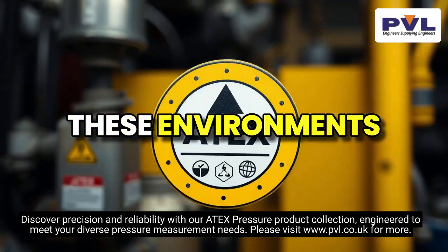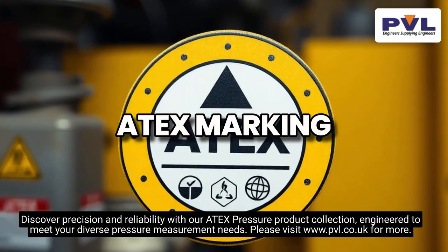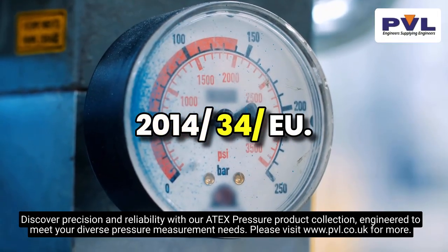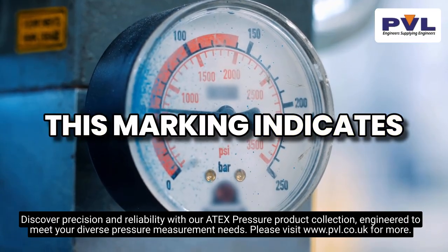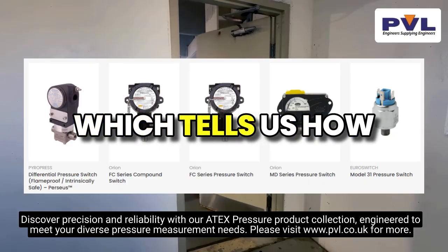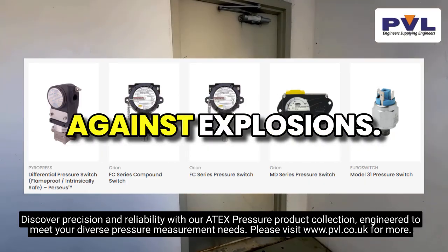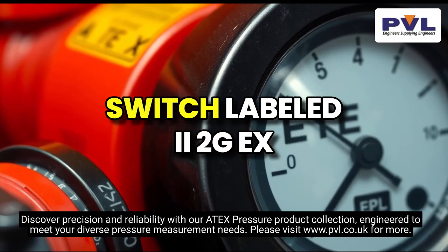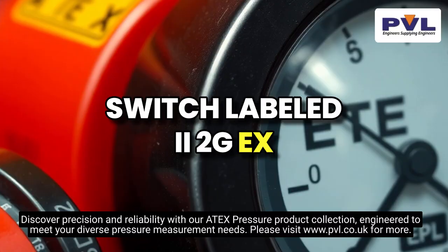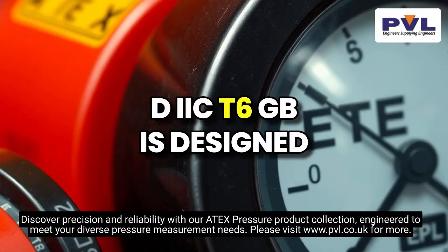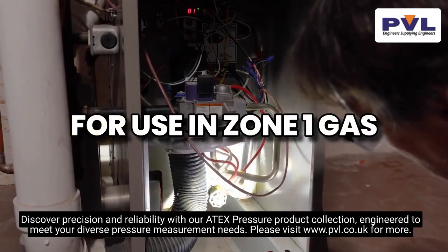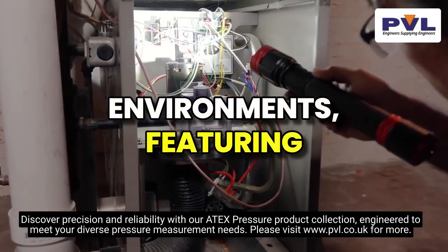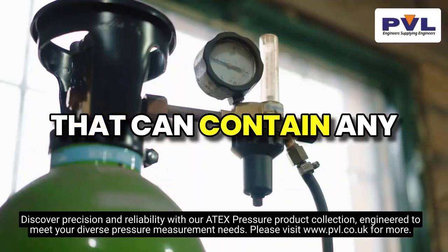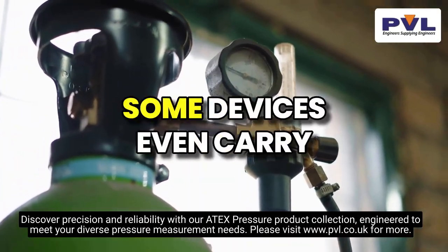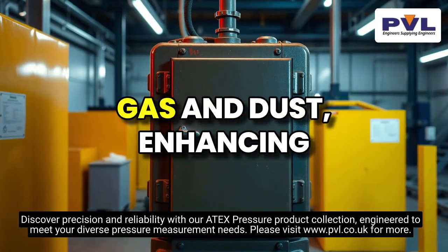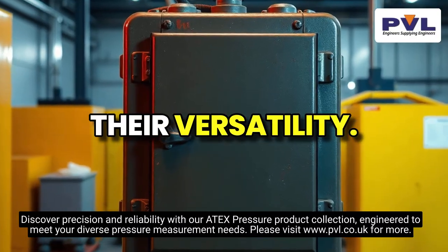Devices used in these environments must feature appropriate ATEX marking under the Directive 2014/34/EU. This marking indicates the equipment protection level, or EPL, which tells us how robust the protection is against explosions. For instance, a pressure switch labeled II 2G Ex d IIC T6 Gb is designed for use in Zone 1 gas environments, featuring a flame-proof enclosure that can contain any ignition that occurs inside. Some devices even carry dual markings for both gas and dust, enhancing their versatility.